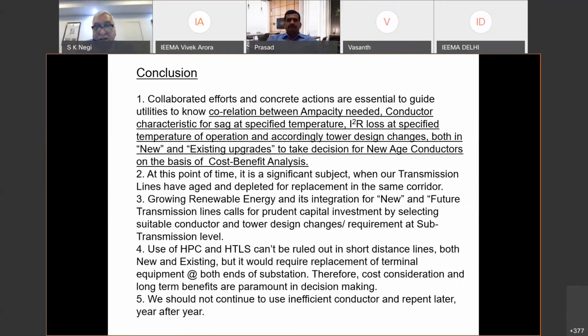Growing renewable energy and its integration for new and future transmission lines calls for a prudent capital investment by selecting a suitable conductor, and tower design changes, either new or existing, required at the sub-transmission level. I have mentioned sub-transmission particularly because renewable energy integration itself will take place from 33 kV, 66 kV onwards. In respect of conductor, maybe from 33 kV up to 66 kV people may go for cables. Okay, fine. But there will be remote areas where 66 kV at least will have overhead lines, and definitely there will be 132 kV, 220 kV lines if it is a 100 megawatt and larger solar park or a wind and hybrid park, which is planned.